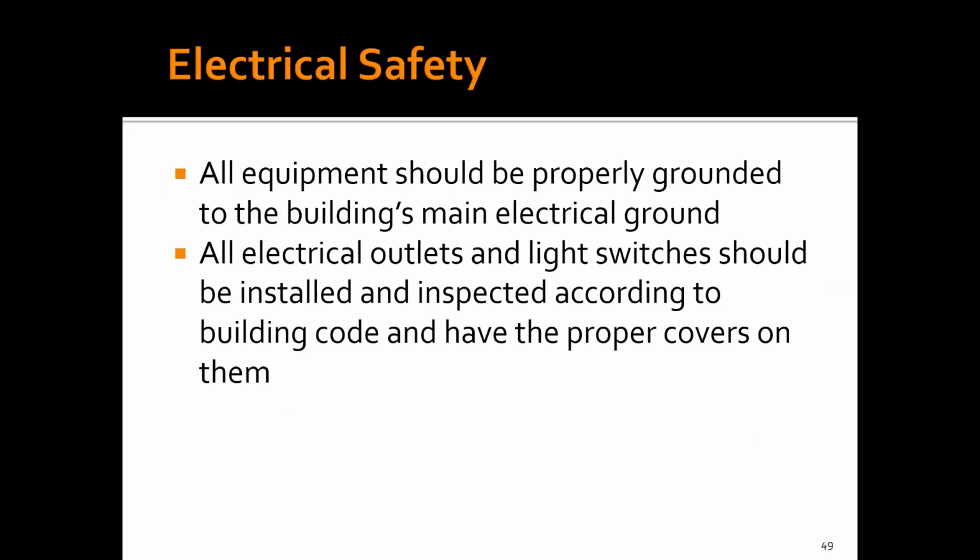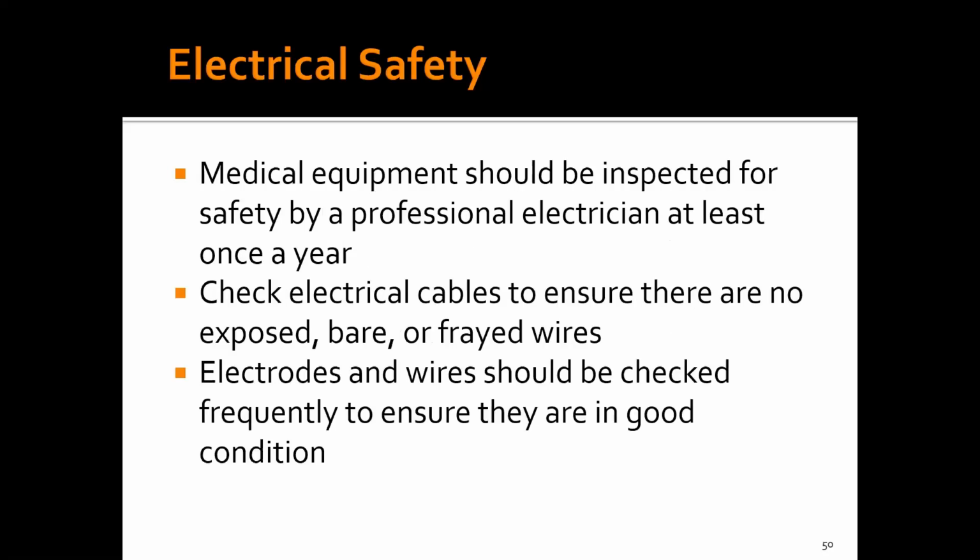So it's important that all the electrical equipment that we utilize is properly grounded and that everything is installed up to code. I know this is where you think, well, how am I supposed to know that? But just working at a reputable place, a reputable lab, in the building, whatever, I don't want to say we should assume, but for the most part, most things are done up to code. Yearly, all medical equipment needs to be inspected by Biomed to check its integrity, its safety, all of that. What is our responsibility is to check all the equipment that we're using on a daily basis.